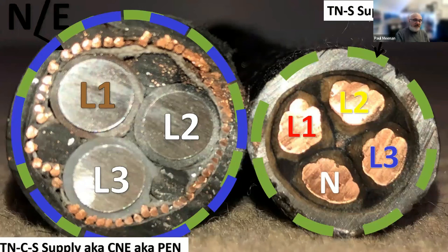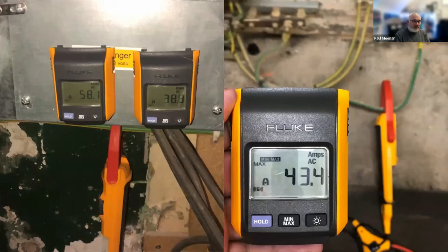Now, the problem with the combined neutral and earth is that if you lose it, then you potentially have diverted neutrals, and you potentially have a rise in voltage. So this is a challenge at the moment in the UK. It's a growing challenge. It's nothing that people need to panic about, but we need to raise the profile so that people can check and ensure they're safe. Safe working is key. Here are some more images to show you how dangerous this can be. Just some clamp meters around earthing conductors, 43 amps, 58 amps. So it is very much real.